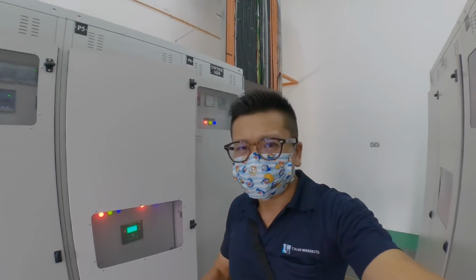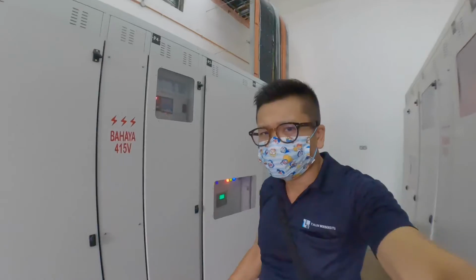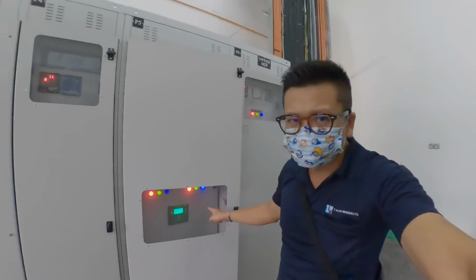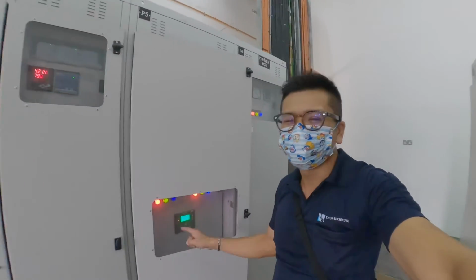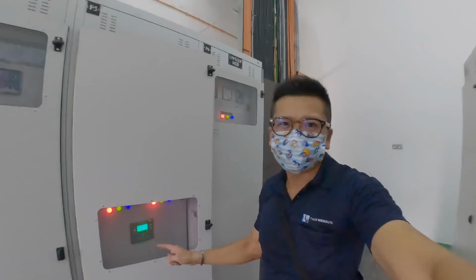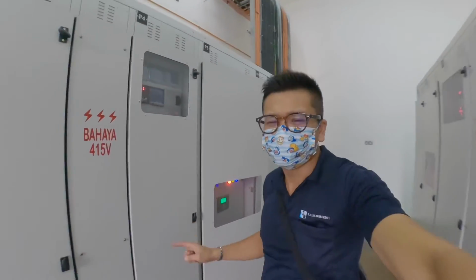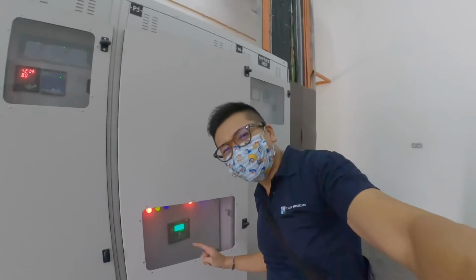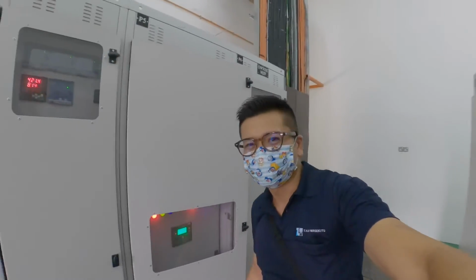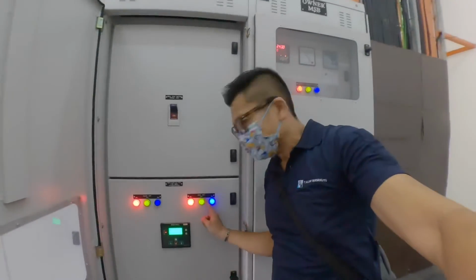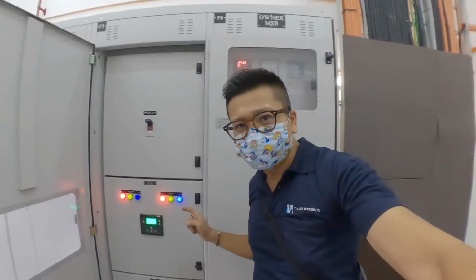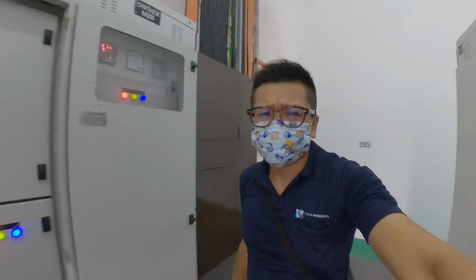Through this way, I will be able to test that the genset is able to start automatically and stop automatically, so that during a TNB power interruption, this ATS panel is able to call the genset to start automatically and to stop automatically. This way I can sleep tight and have no worry that during a TNB power interruption, the genset will automatically back up the lift power supply and also the essential power supply, which is this panel. Now we just wait for the genset to stop automatically. As I removed this, the genset will run a shutdown timer, which is probably 2 to 3 minutes, depending on the size of the genset, and is adjustable at the AMF panel.